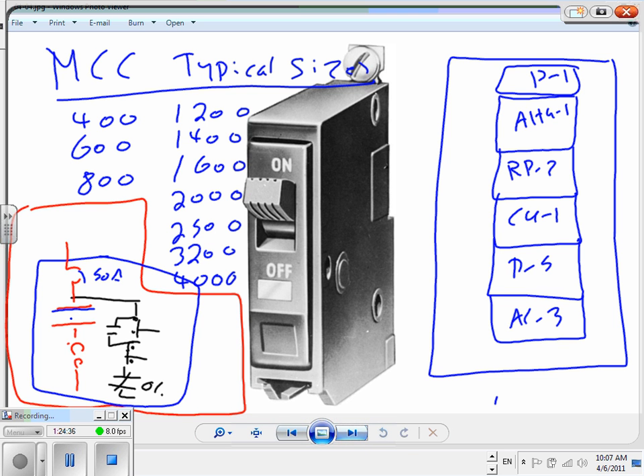Where would you use an MCC? Process control. Any area that needs process control, manufacturing process control, is a big deal for them. I've seen it personally in what we call not data centers, but wastewater treatment plants. They love them in wastewater treatment plants. They actually make them service entrance equipment. All you have is just a big MCC that's 12 foot wide, and they bring the service to one section of it with a 1200 amp disconnect, and then the whole section is an MCC.